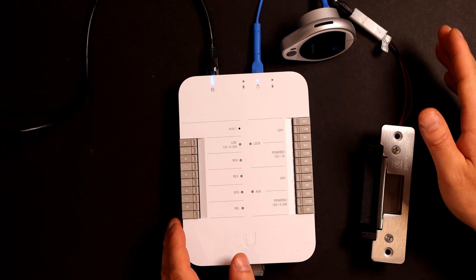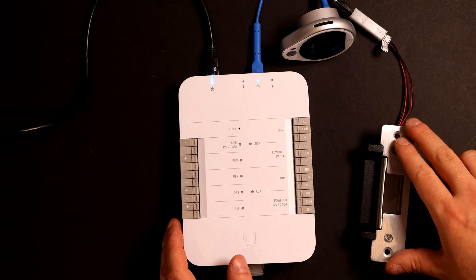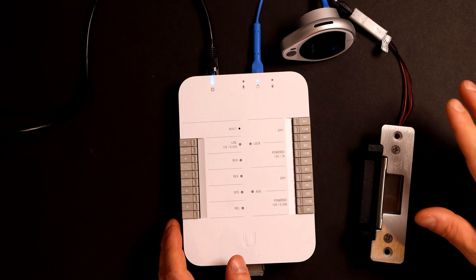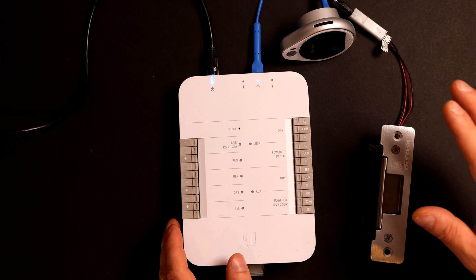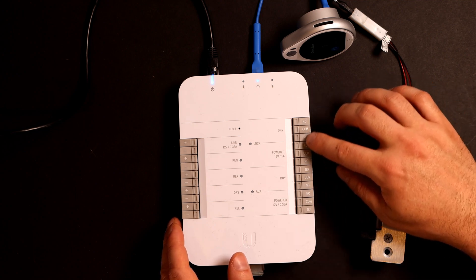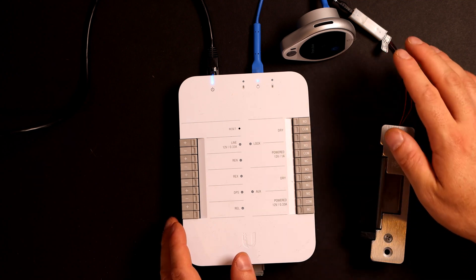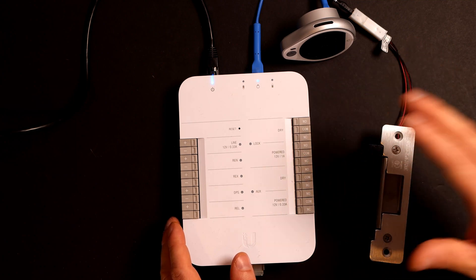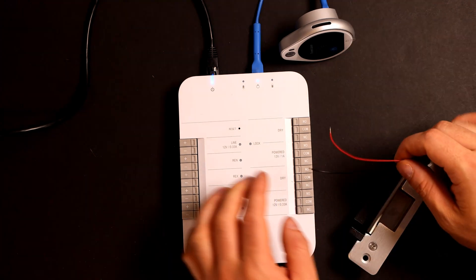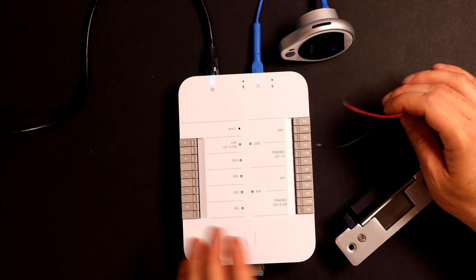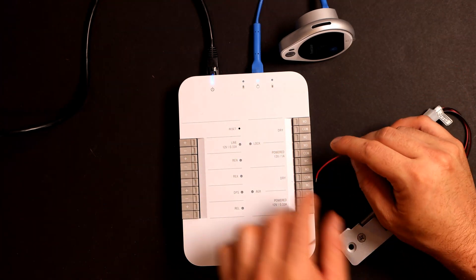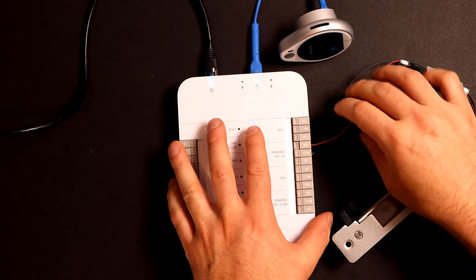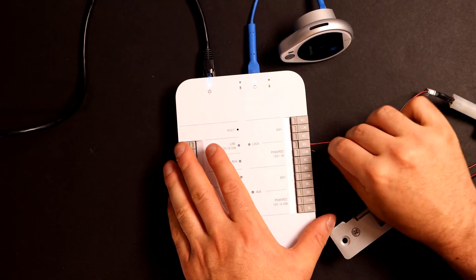If we're using an external battery to power up all of our accessories, our strikes, our mag locks, or any of our motion sensors, then we would put that on our dry relays. If we want to power it up using the UniFi Access Hub, it needs to be a 12 volt strike or a 12 volt mag lock. So since I'm using this in a fail secure mode, we need to wire it up where our red is going to normally open, and then our black is going to the com port.